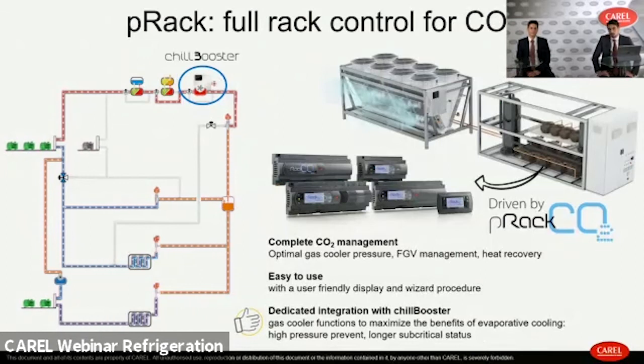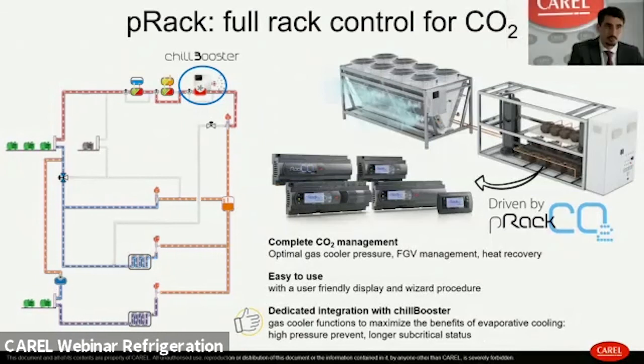So let's focus on pRack, that is our best solution for transcritical CO2. That controller is able to manage the compressor rack as well as the gas cooler. And in this case, it has some specific functions thought and designed to control the chillBooster. What I mean by that is it can be integrated as a safety function to avoid a high pressure alarm, and it's turned on and off directly by the logic of the pRack.